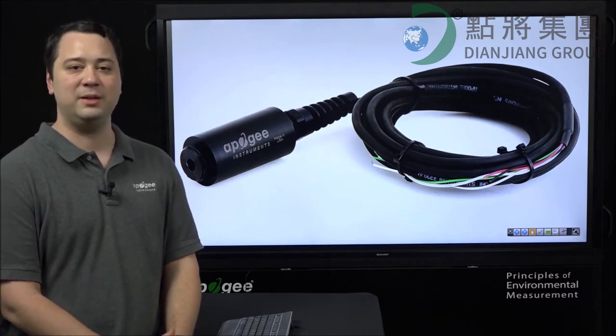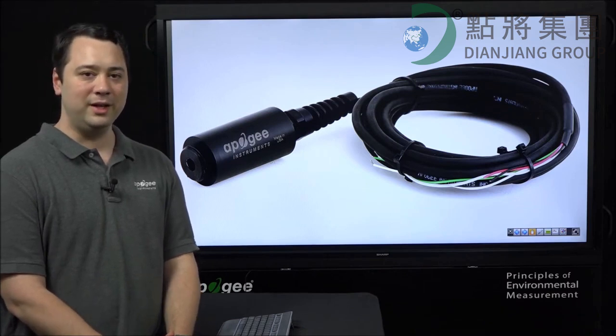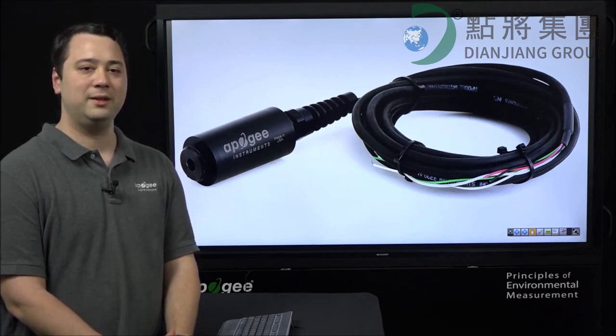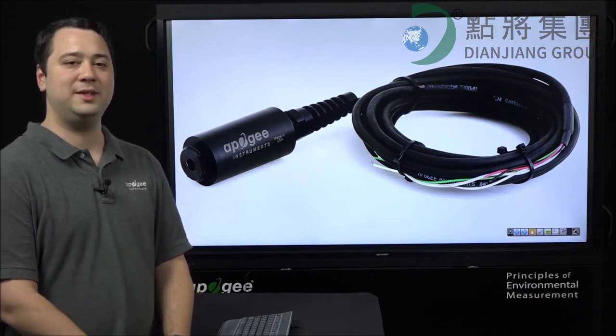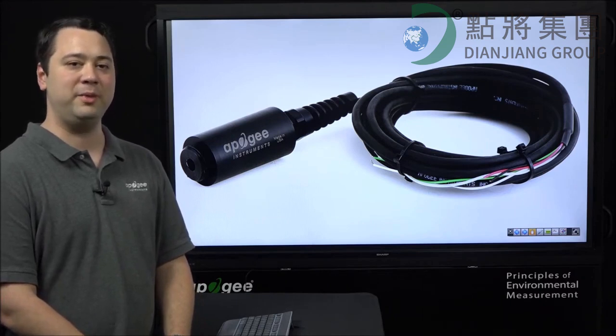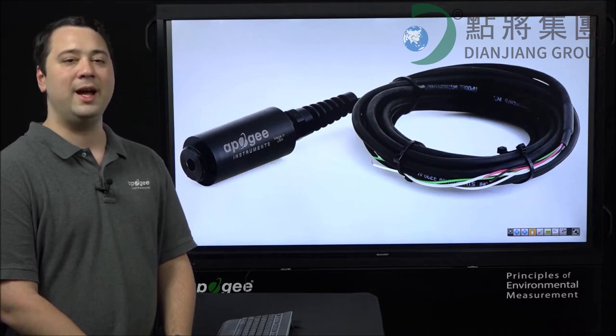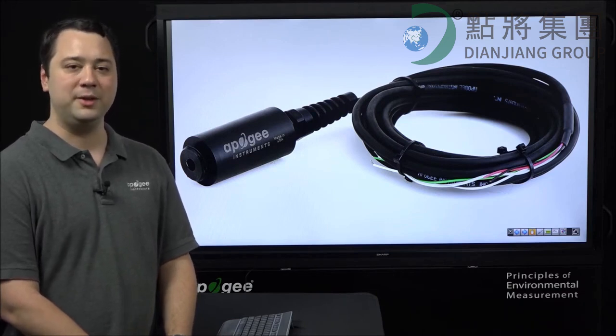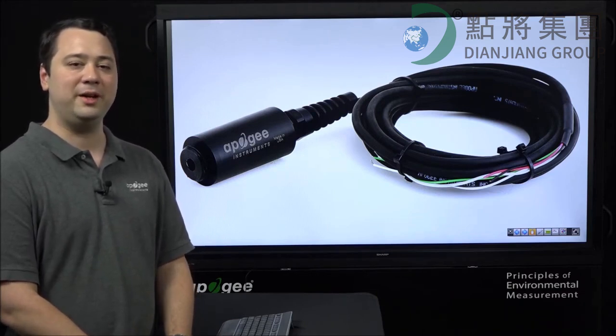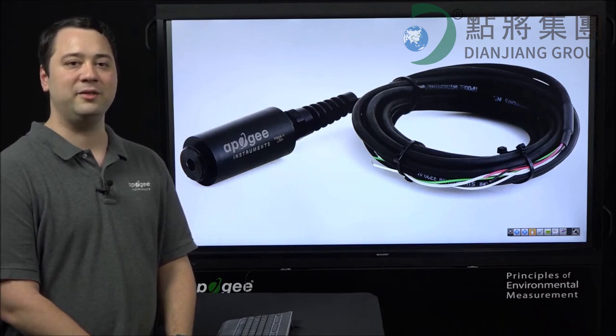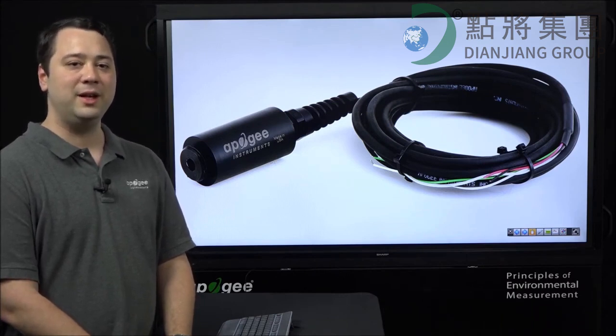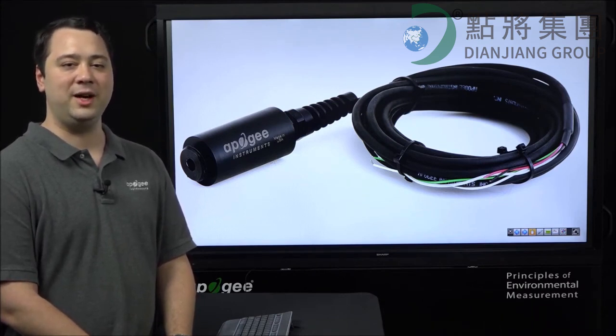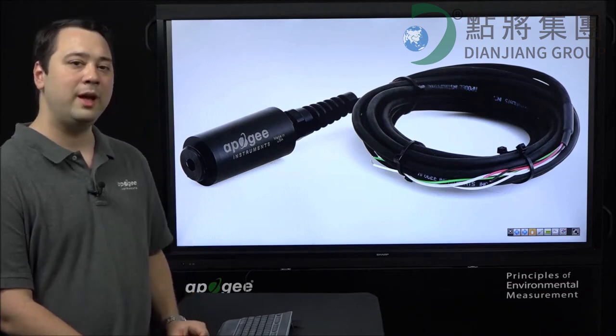Once you have this calibration millivolt reading, you will want to use it in the formulas listed in the SO100 and 200 manuals in order to obtain your calibration multiplier and calibration offset. Once you have this calibration multiplier and offset, you can use it to convert the sensor's millivolt signal into a measure of relative oxygen concentration.